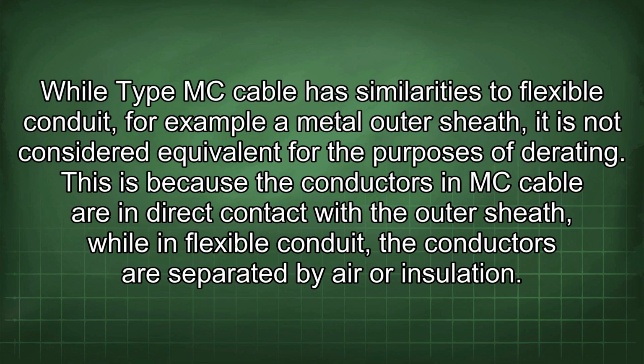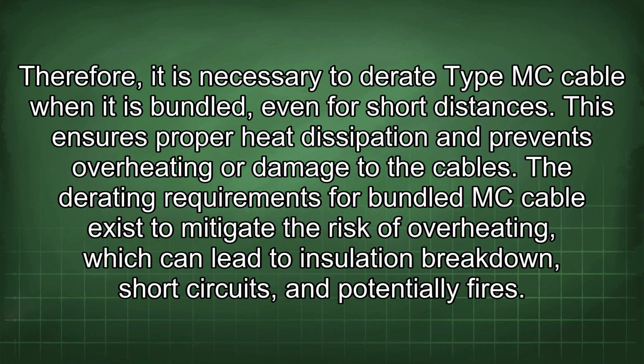While Type MC cable has similarities to flexible conduit, for example a metal outer sheath, it is not considered equivalent for the purposes of derating. This is because the conductors in MC cable are in direct contact with the outer sheath, while in flexible conduit the conductors are separated by air or insulation. Therefore, it is necessary to derate Type MC cable when it is bundled, even for short distances. This ensures proper heat dissipation and prevents overheating or damage to the cables.